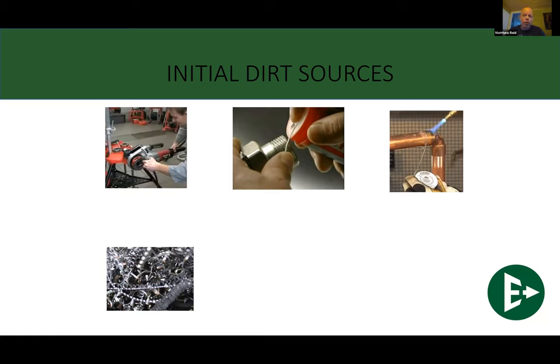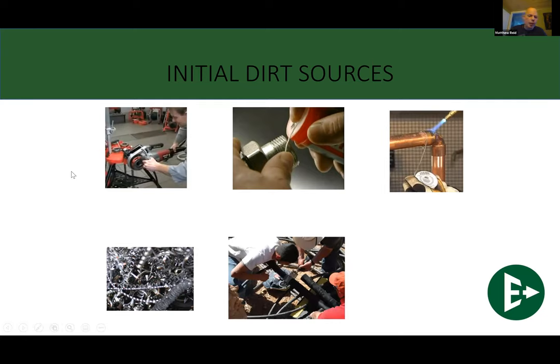If you are doing a copper system and you're doing solvents, your flux from your solder can get in there. Even little solder balls on the inside can let loose and come across. A little solder ball hitting the impeller of a pump could be game over right there. Not in all cases; in some cases it is going to pass through and we'll catch it somehow, but we're talking worst case scenarios. And that's how these pieces can get in there.